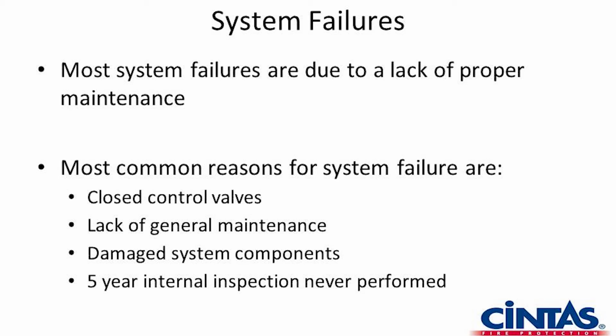On an annual inspection or a quarterly inspection, we're looking at gauges, pipes, sprinklers, things of that nature. On the 5-year inspection, we look inside the pipe. We're looking for buildup, sludge, foreign objects, anything that could be in the pipe that would hinder the flow of water or could slide into the orifice of the sprinkler head that is discharging and prevent water from flowing. So that is some of the things that take place on the 5-year inspection.